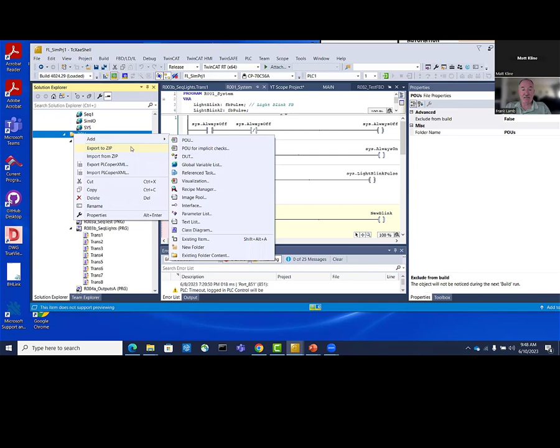There's what the structured text version would look like: if runtime seconds .q is up, then add a minute, right, and reset runtime seconds. So this is a cascading timer like I have in my advanced PLC book. I give an example of cascading timers and counters. If minutes greater than or equal to 60, then hours equals hours plus 1. That's just an accumulator. Reset minutes back to 0, and it's an if statement.